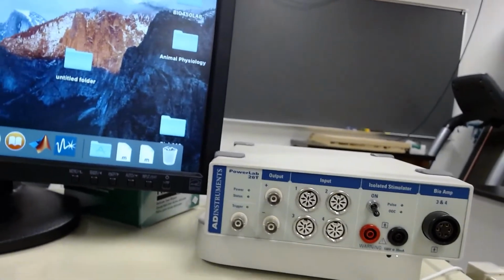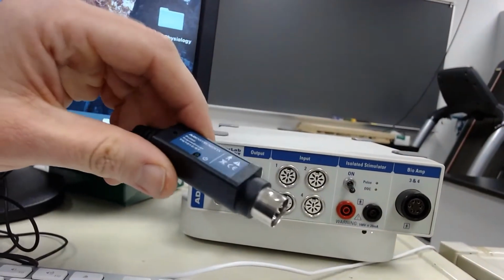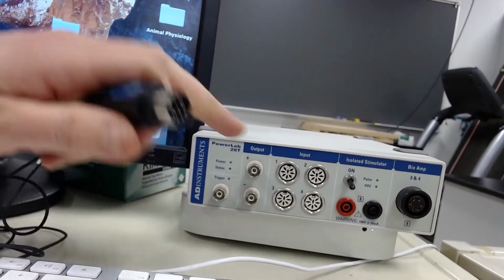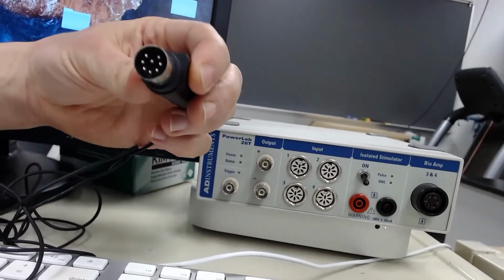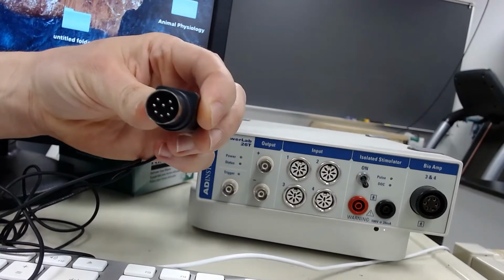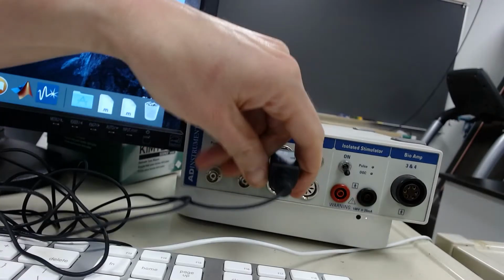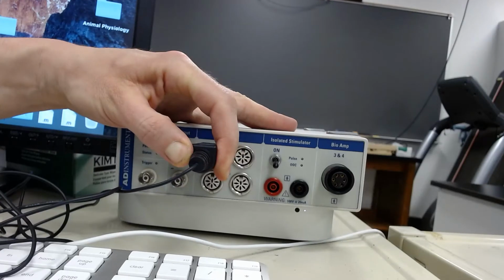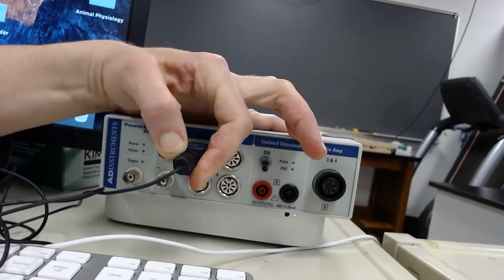But for right now, we're just going to plug this finger pulse transducer into one of these inputs. You'll notice there's some directionality to this, so I'm just going to plug it in right up here. You want to make sure that's in there securely. Hard to do with just one hand.